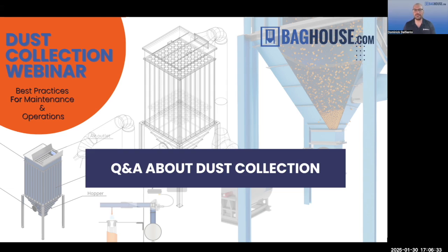When you have a system that's undersized, like we said, it's a spectrum. It goes from working really well to not working so well to meh to not working at all. When the system's undersized, a few things happen that you'll notice. It'll still be working, but you'll have a lot of times problems with a lot of holes from abrasion, right? You have a lot of abrasion at the bottoms of the bags, especially, and that's because you're pushing so much air through a small box, the air speed inside is so fast that a lot of times it causes more abrasion on the bottoms than we normally would see.